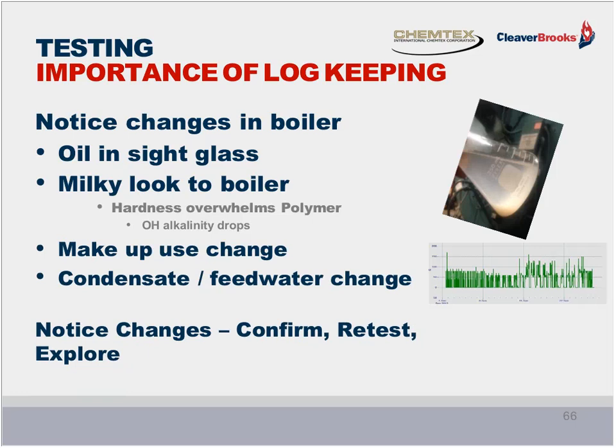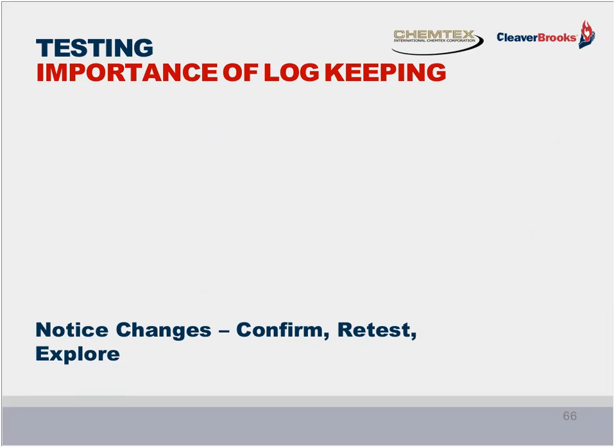It's so critical that you notice the changes, that you confirm them, that if you've got any questions, you retest and you explore to find out what caused these problems. Because if you don't take action, if you don't notice that there's oil in the sight glass, if you don't notice that there's a change in makeup use, you can end up with failures.